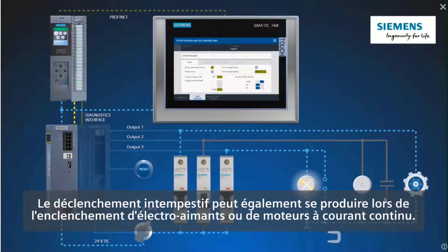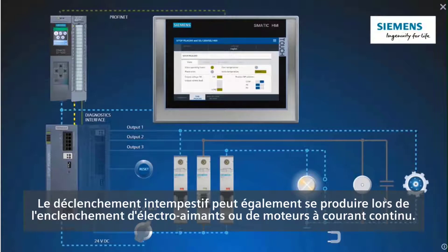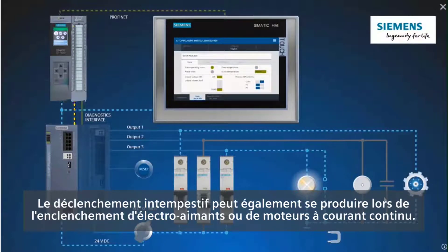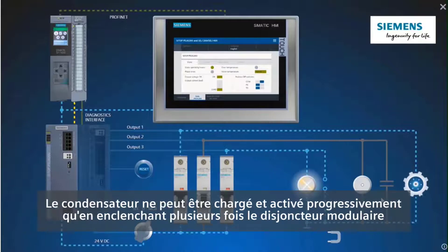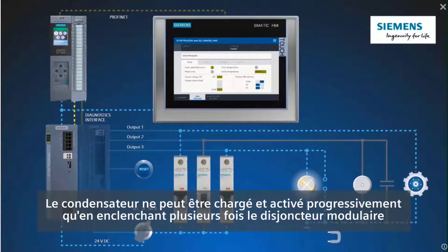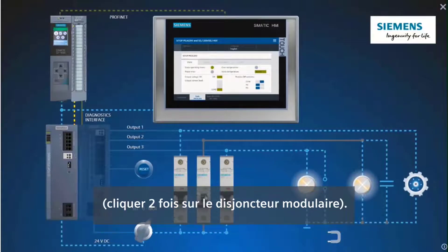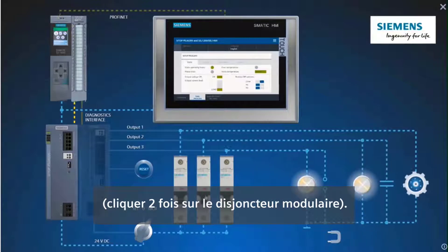The unintentional tripping can also happen when switching on electromagnets or DC motors. Only by switching on the miniature circuit breaker several times can the capacitor be successfully charged and switched on.